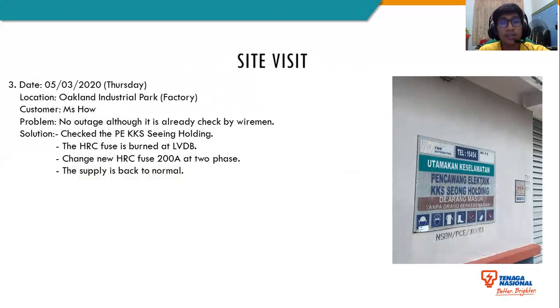Okay, the last one is at the Oakland Industrial Park. It's a factory. The customer is Miss Howe. The problem is no supply at the factory, although it was already checked by the wireman. So we checked at the Pejabat Electric KKS Seong Holding. We noticed that the HRC fuse is burnt out at the LVDB board. We changed the new HRC fuse to 200A at 2-phase. Then the supply went back to normal.